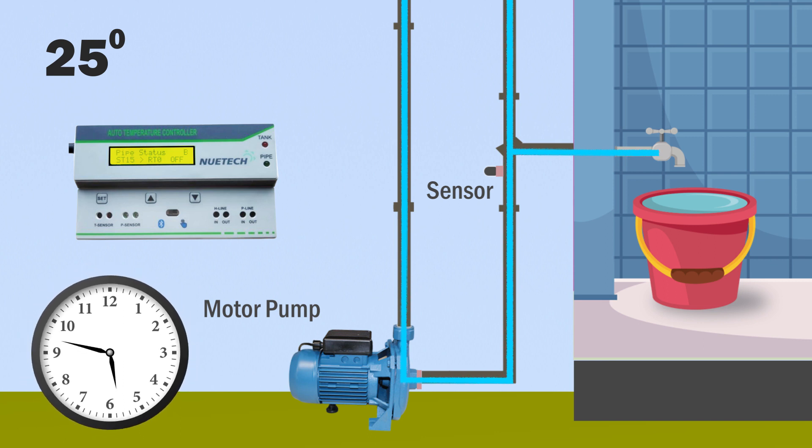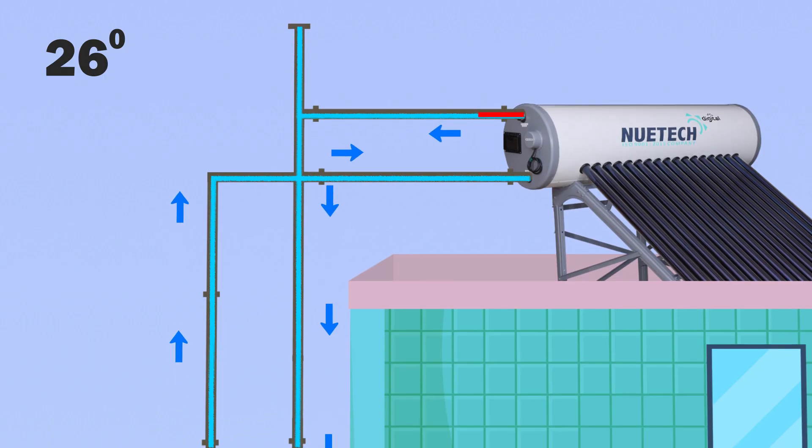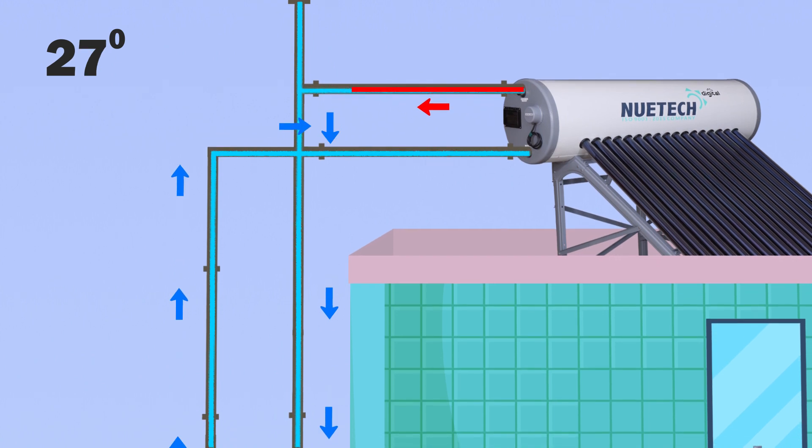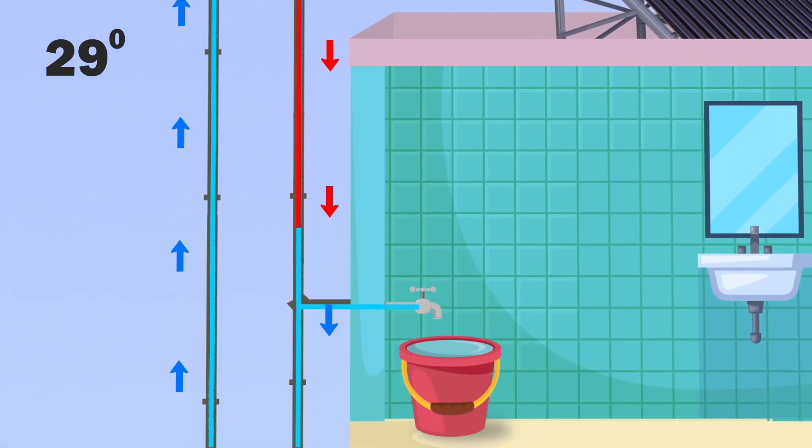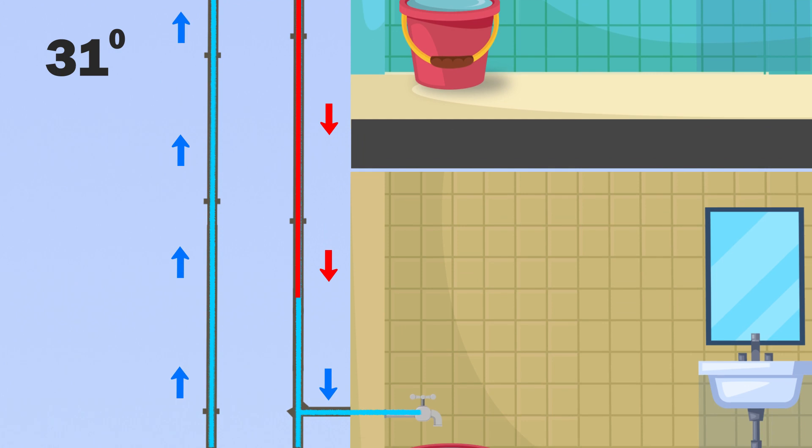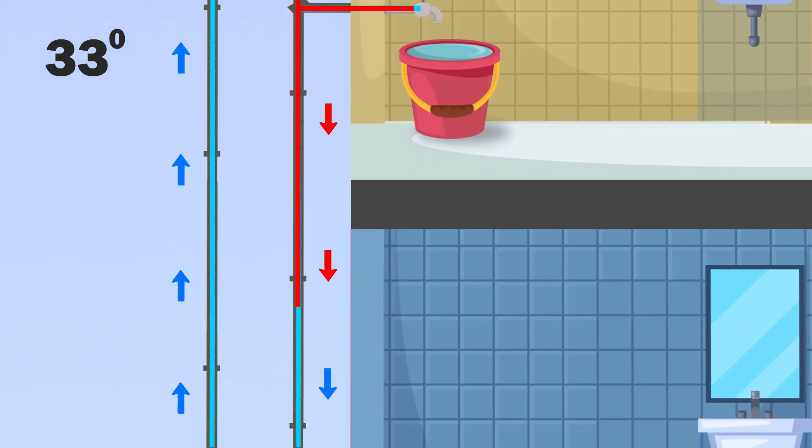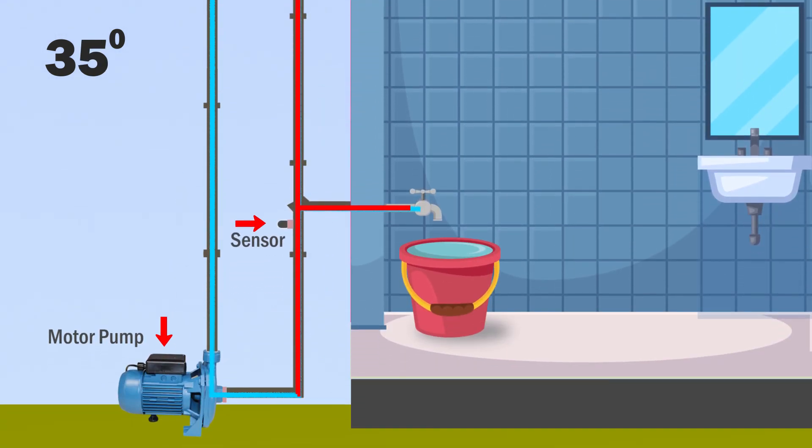For example, if the time is set for 6-9 AM and the pipeline temperature is set at 35 degrees, the return line pump will turn on so that the cold water filled in the pipeline does not reach the solar tank. When the hot water in the pipe reaches 35 degrees, the pump will be turned off immediately through the sensor.